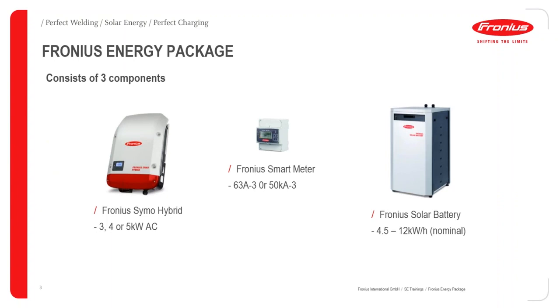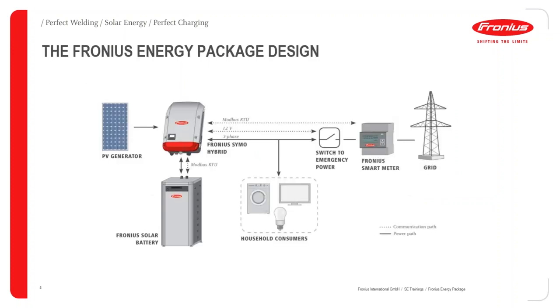So the Fronius energy package consists of three components. That's the Symo Hybrid, which comes in 3, 4 or 5 kilowatts. The Fronius smart meter, being three-phase, of course, because it's a three-phase inverter, so you'll need the three-phase meter. That comes in a 63 amp or the 50 kA, which is the larger. And then you've got the Fronius solar battery, which is 4.5 kilowatt hours to 12 kilowatt hours nominal, at 80% depth of discharge.